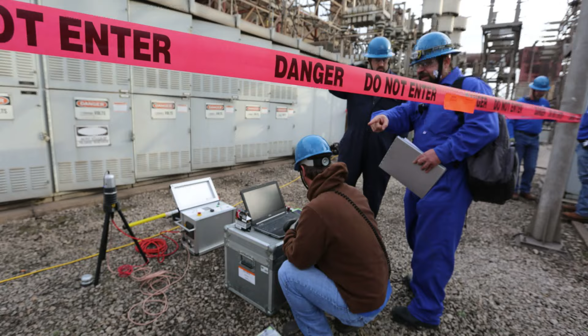I would say that when you look at the NETA standards, they're written to specifically look at the industry standard, which very low frequency is probably your best bang for your buck when it comes to testing these. DC was the rage and the standard years ago, and it's fallen out of vogue for some degree. And VLF is that sweet spot of providing enough value for the test while also not being too cumbersome to operate. The way that I try and approach a lot of these medium voltage testing questions from companies is looking at what are your needs.